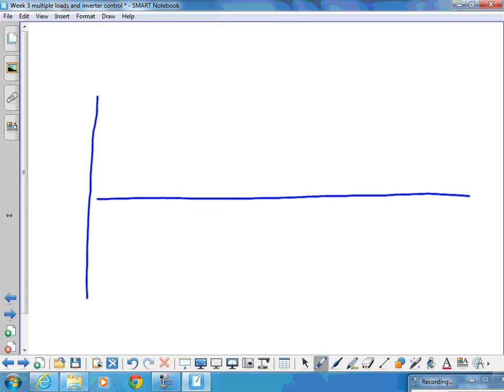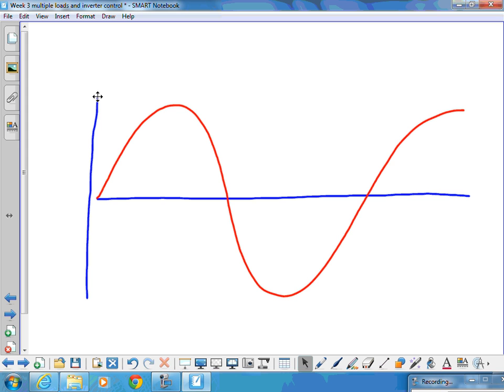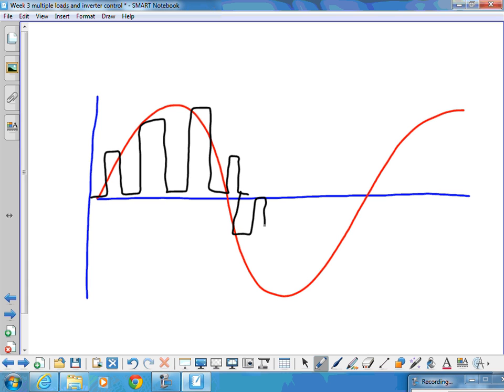One of probably the most common ways for this sine wave to be recreated by the electronics is, remember what we're looking for, what the inverter does is recreate that using pulse width modulation. So it'll send out a square wave where the pulses get wider when you want the voltage to be higher. I'm not very good at drawing that, but the pulse width gets bigger when you want it to be higher. So you don't end up with a perfect sine wave, you end up with a notchy one, like you saw on the diagrams before.